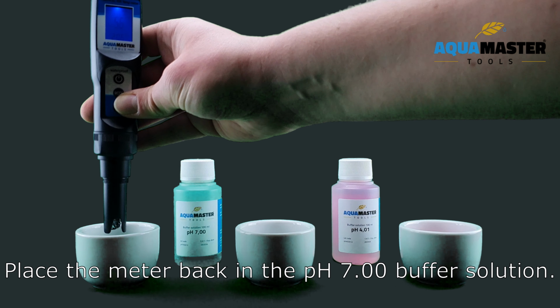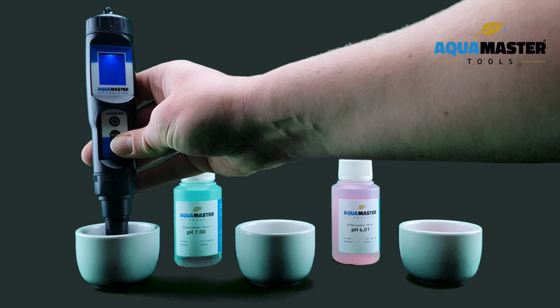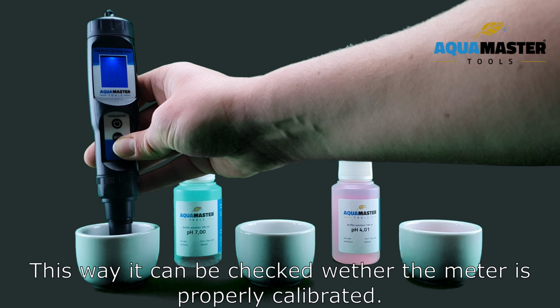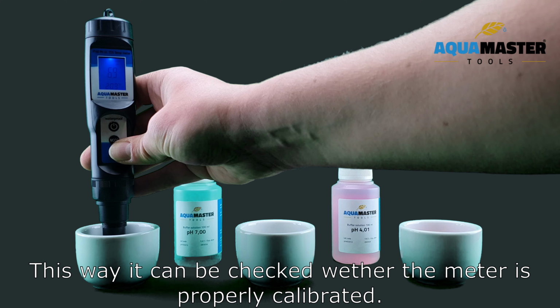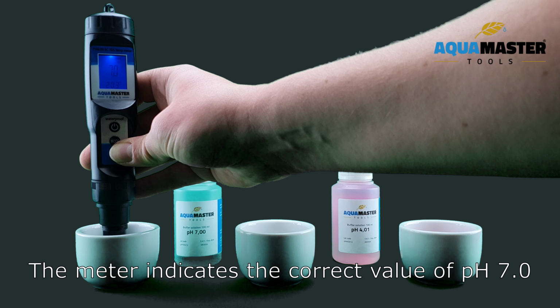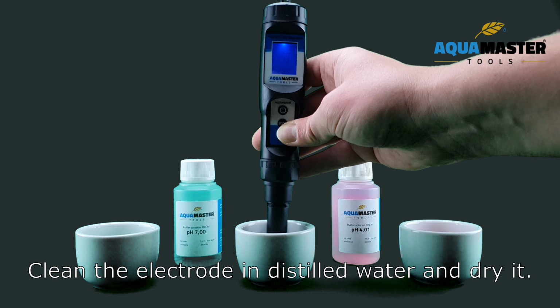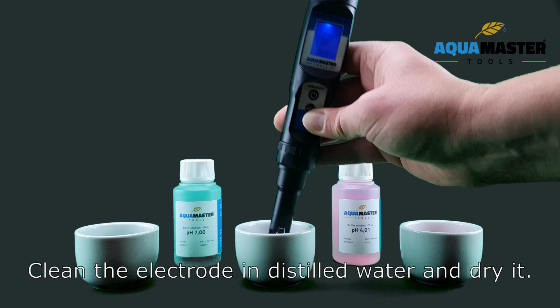Place the meter back in the pH 7.00 buffer solution. This way it can be checked whether the meter is properly calibrated. The meter indicates the correct value of pH 7.0. Clean the electrode in distilled water and dry it.